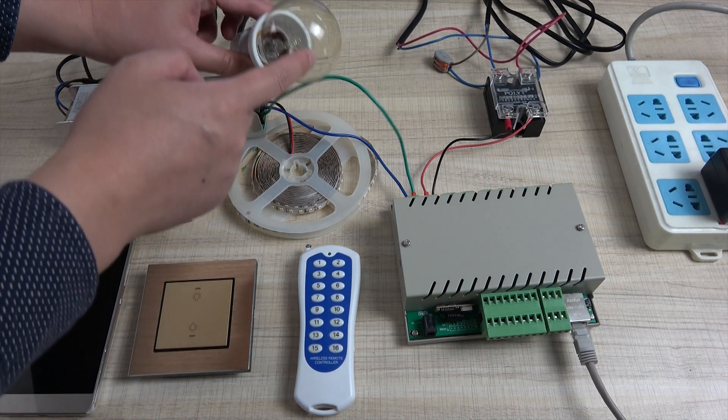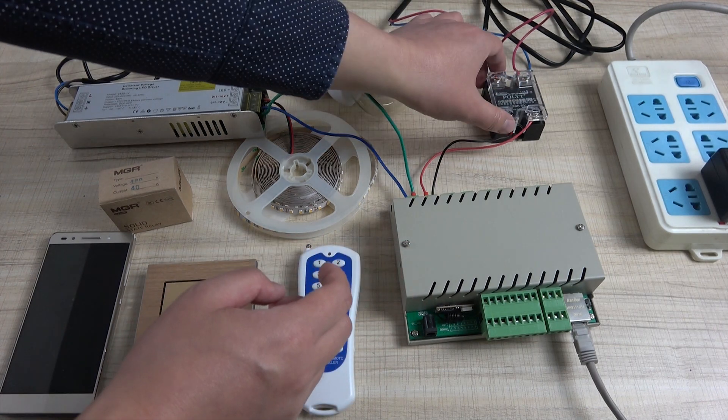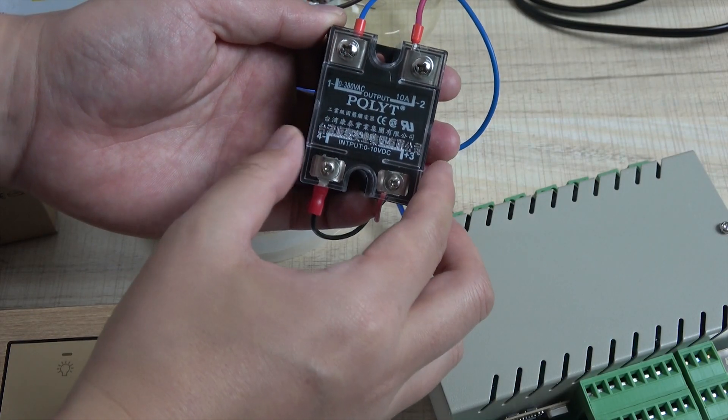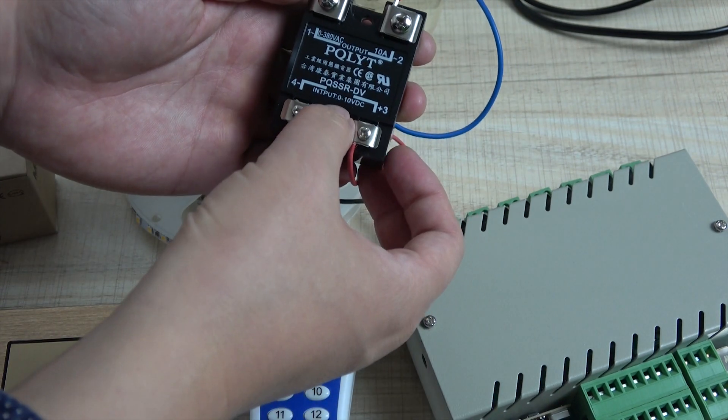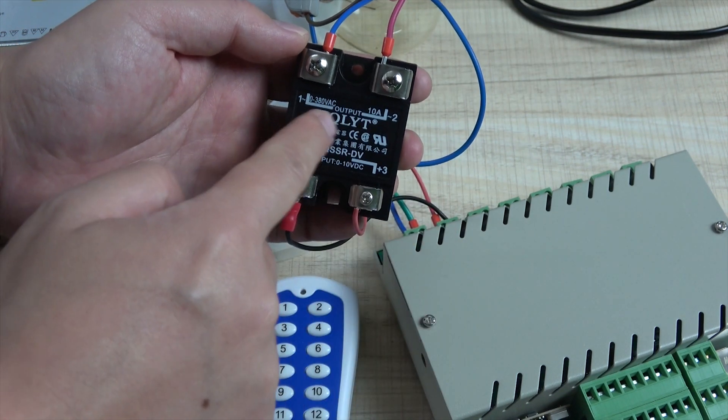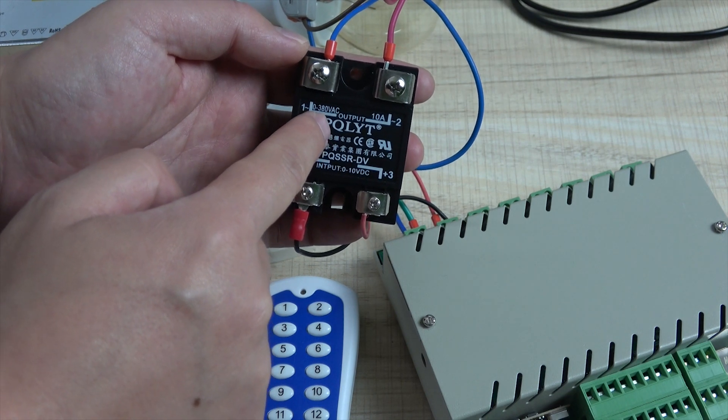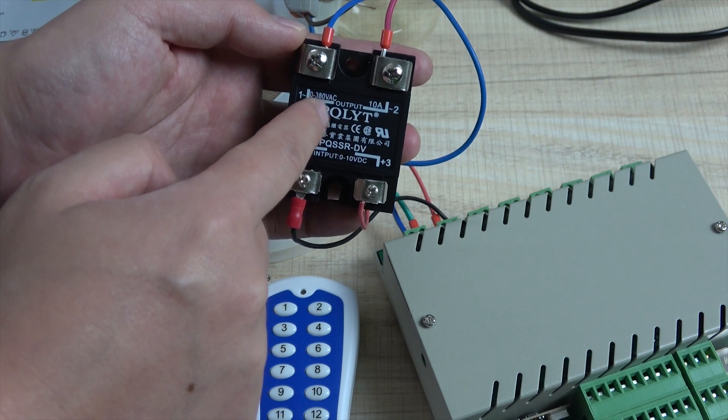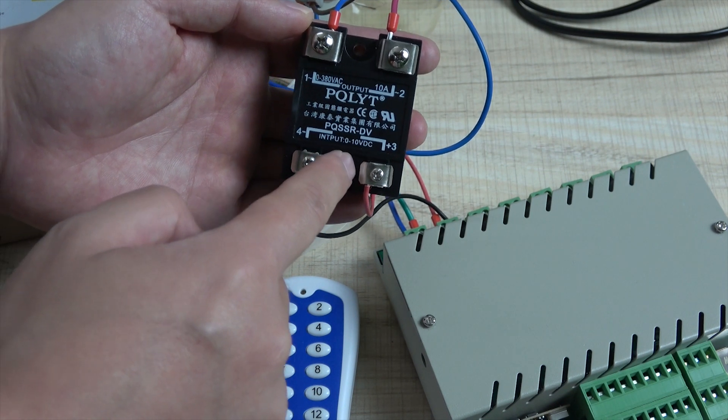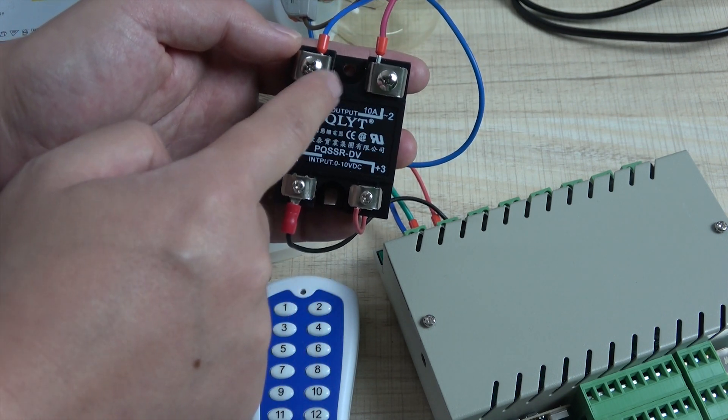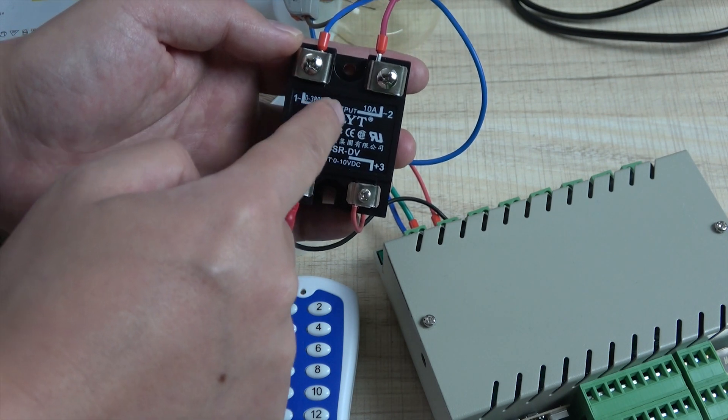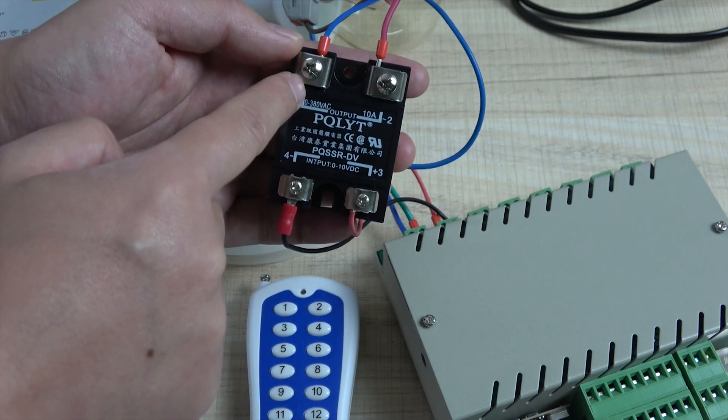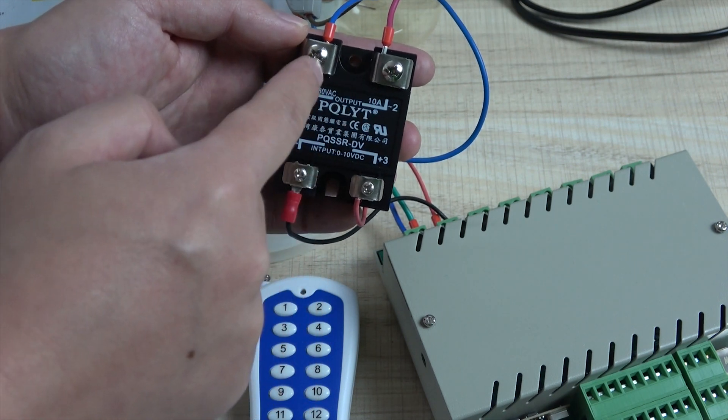And when you control this 220V load, we need to use this SSR. We can see this SSR is special. We can open the case. This input is 0 to 10V. And this is output. Output, it max supports 380V, but we use AC 220V. So when we input 0V, this will output 0V. And when we input 10V, this will output 220V voltage. If you connect with 380V, it also will output 380V.